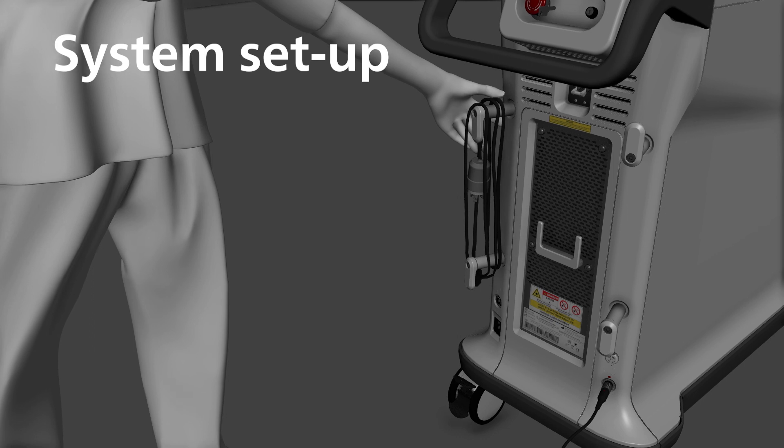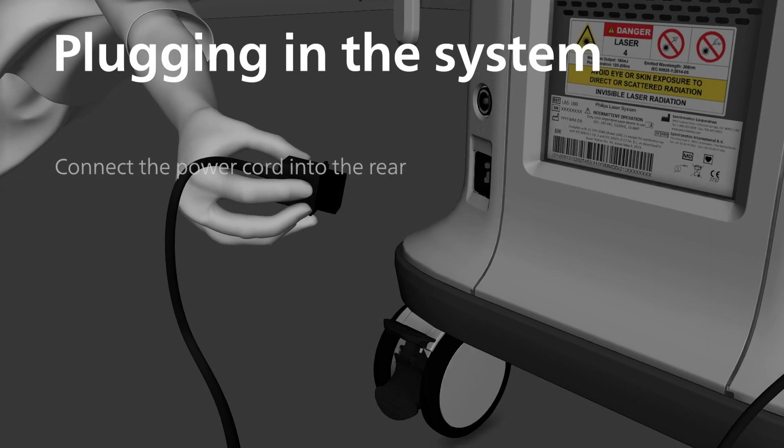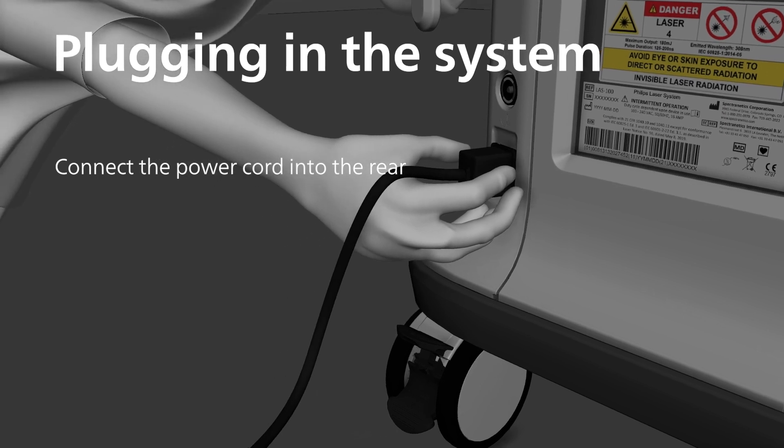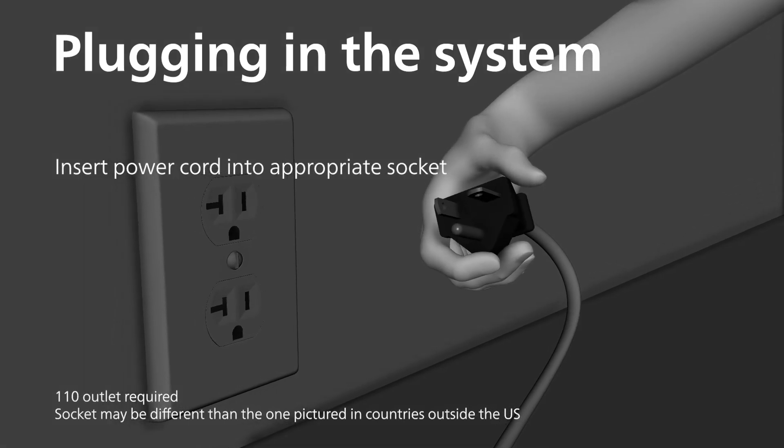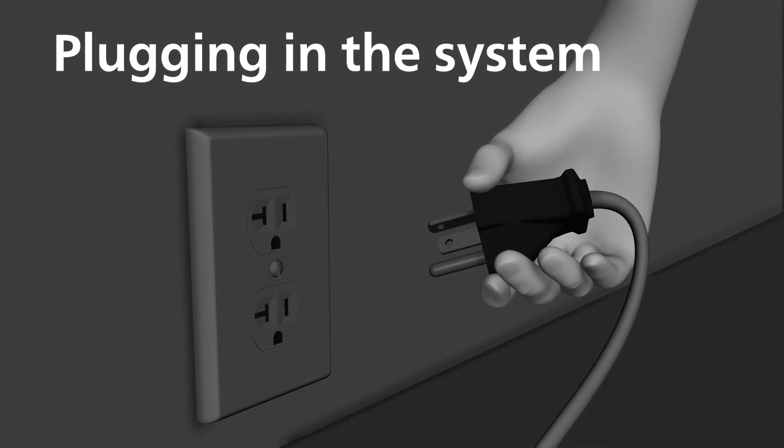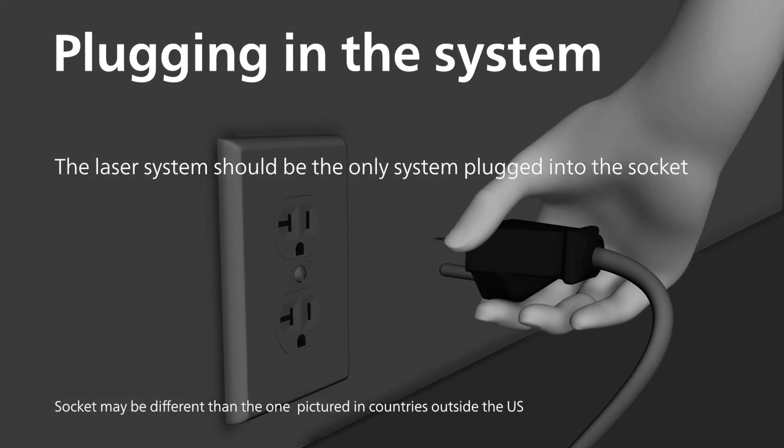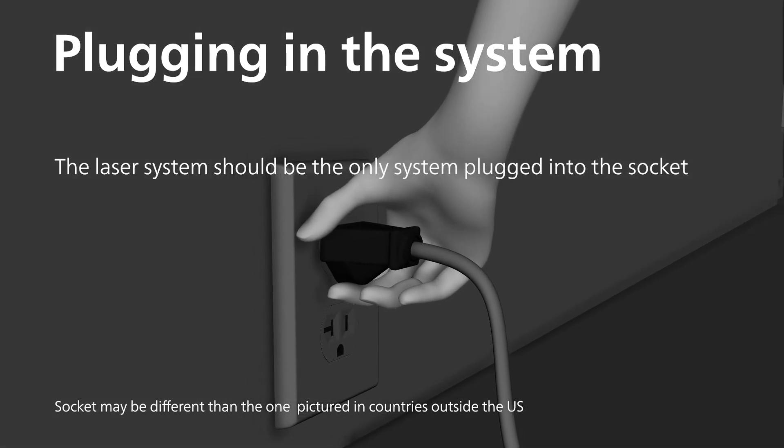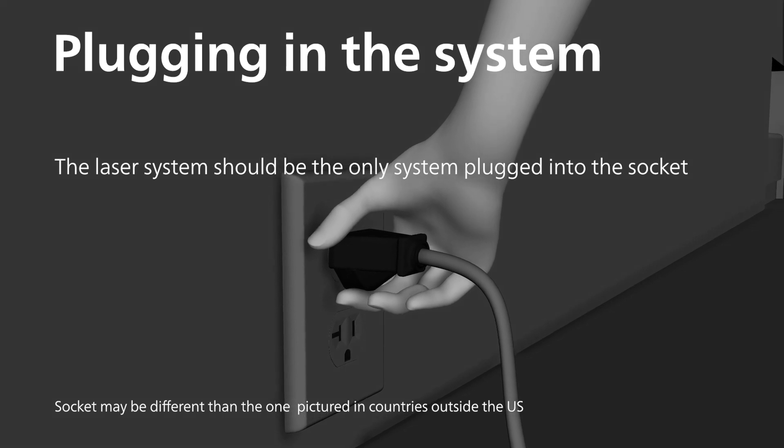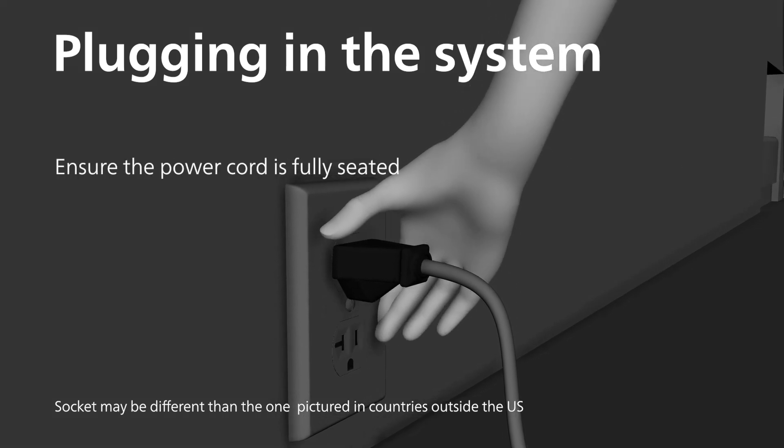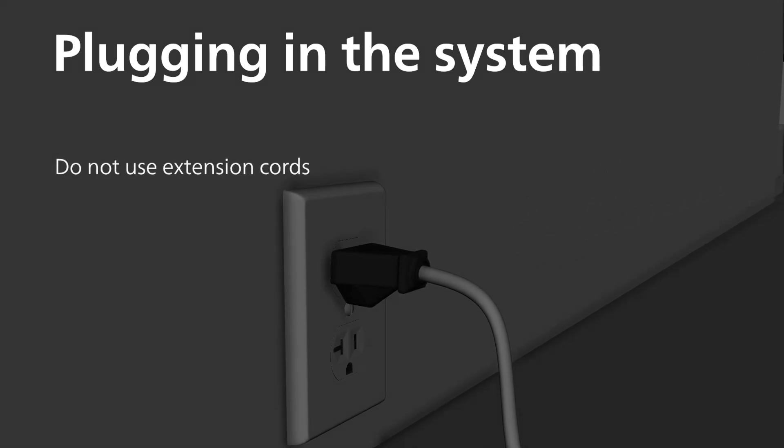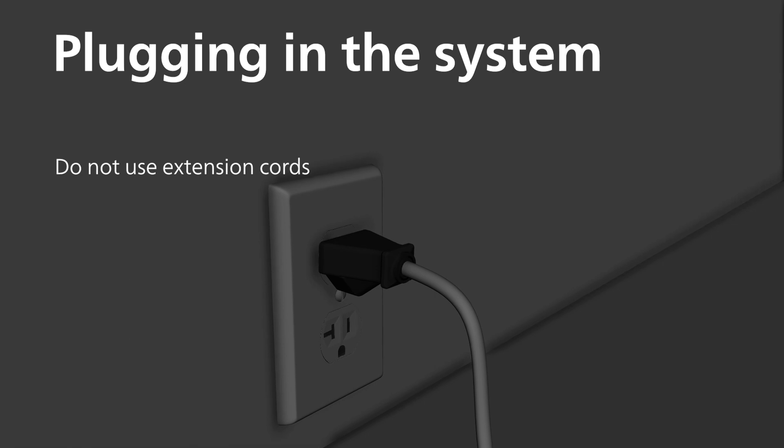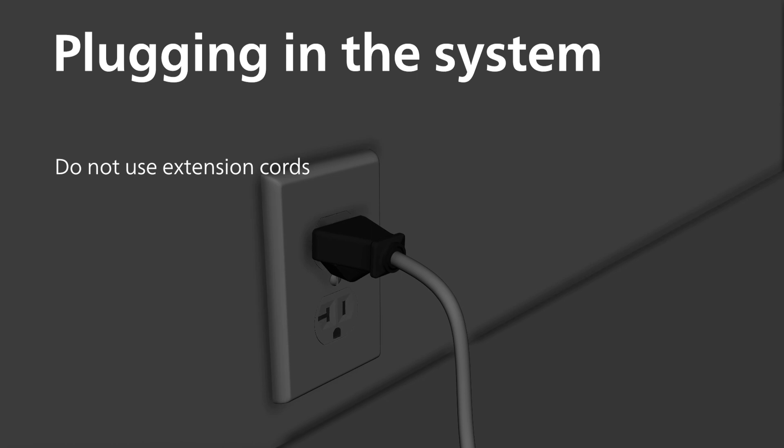You are now ready to plug in the system. Connect the power cord into the socket on the rear of the system. Insert the other end of the power cord into an appropriate socket. The laser system should be the only system plugged into the socket. Using a lower capacity dedicated circuit may trigger the system circuit breaker. Ensure the power cord is fully seated. Do not use extension cords. The 15-foot cord that is included with the system should be usable in multiple sockets in a lab. An extension cord may not supply the expected amount of power to the system.